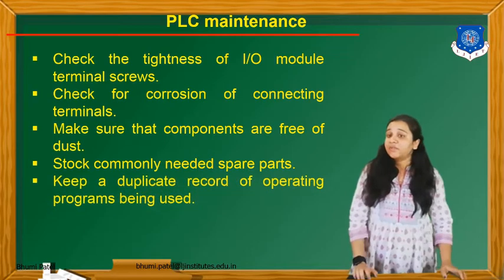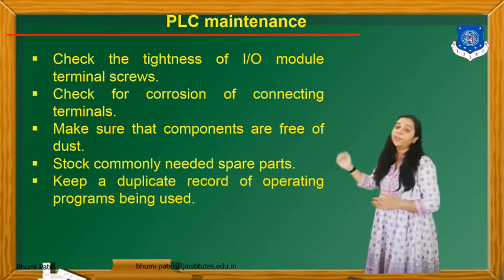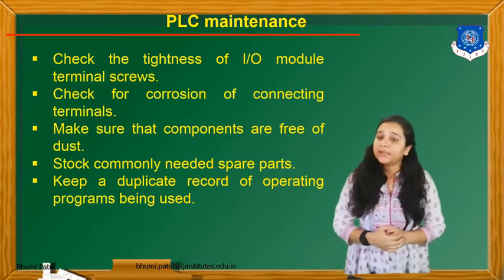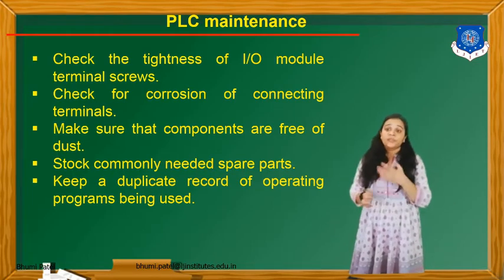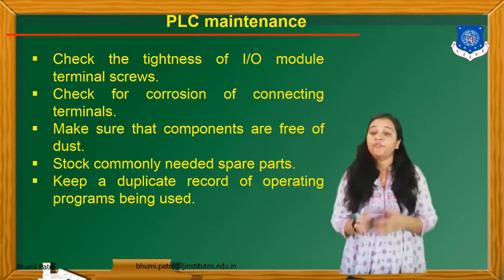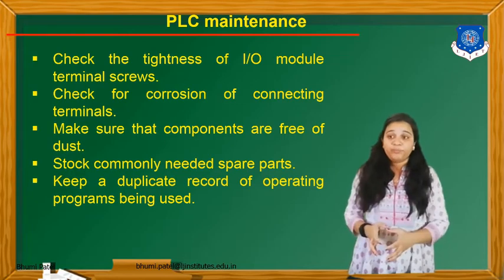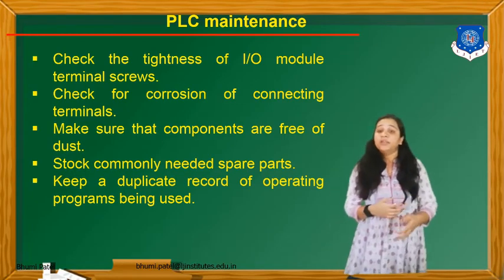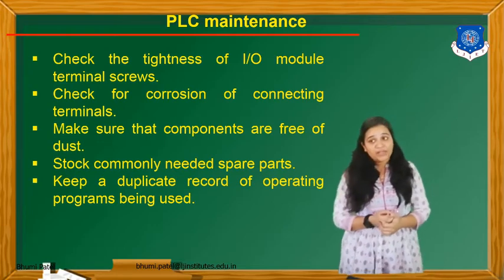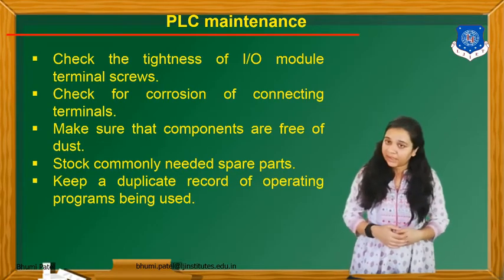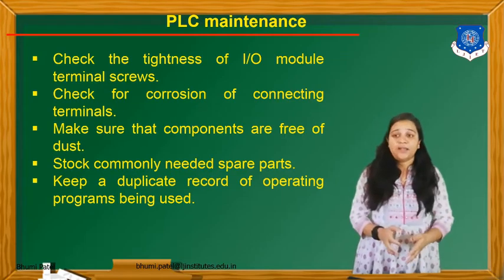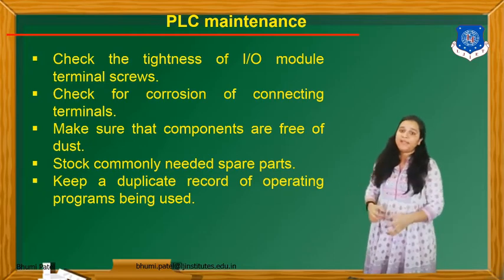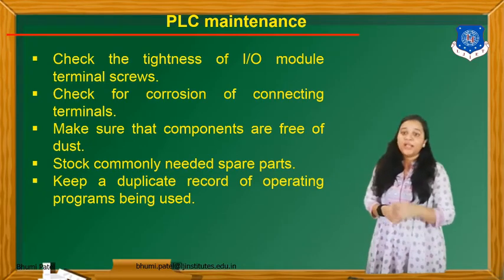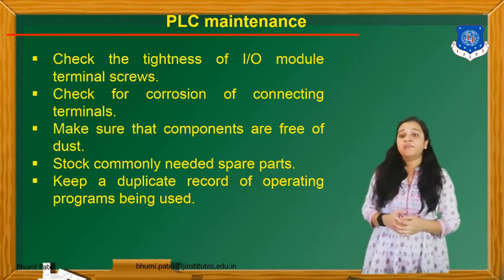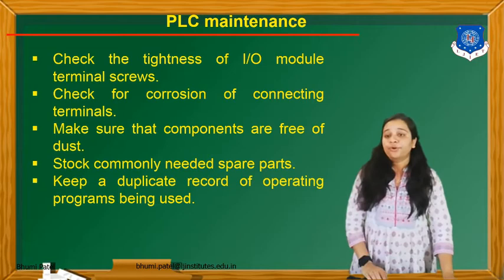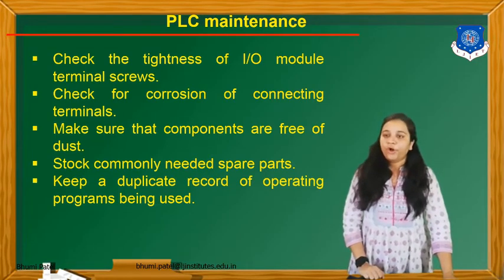Next, keep a duplicate record of the operating program being used. Since the PLC hardware runs the system 24 hours, 7 days a week, we must keep a duplicate record of the programming done for this system. So in future, if any error occurs or difficulty arises, we can easily copy and paste this duplicate program into the PLC software, load it into the hardware, and restore our system.